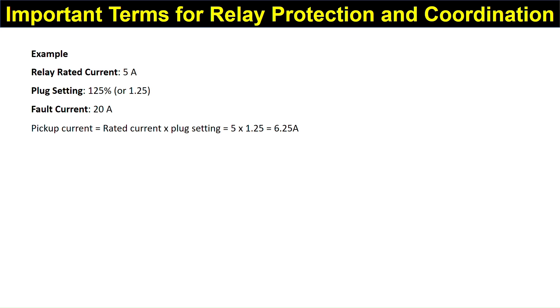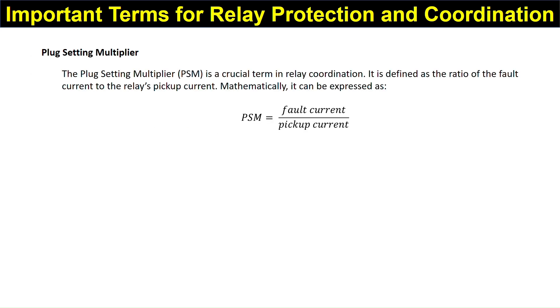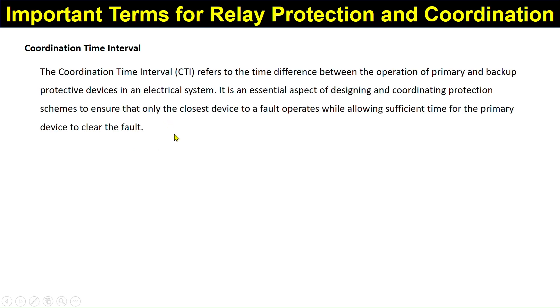Plug Setting Multiplier, or PSM, is an important term in relay coordination. It is defined as the ratio of the fault current to the relay pickup current: PSM = Fault Current / Pickup Current. The PSM is a way to measure how much stronger the fault current is compared to the minimum current needed to trigger the relay.